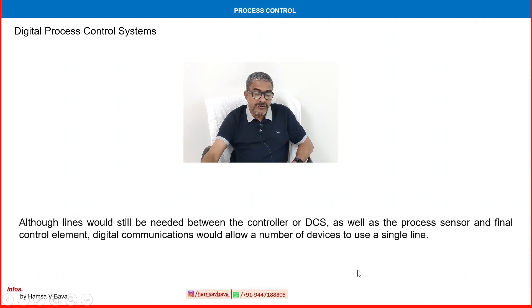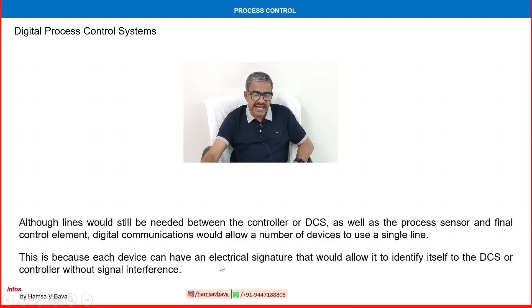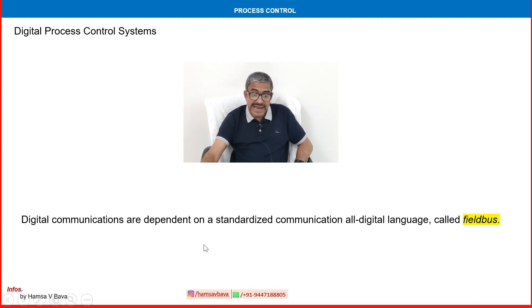Although lines would still be needed between the controller or DCS, the process sensors, and the final control element, digital communication allows a number of devices to share a single line. Each device can have an electrical signature that identifies itself to the DCS or controller without signal interference. Digital communications depend on a standardized communication language called fieldbus.